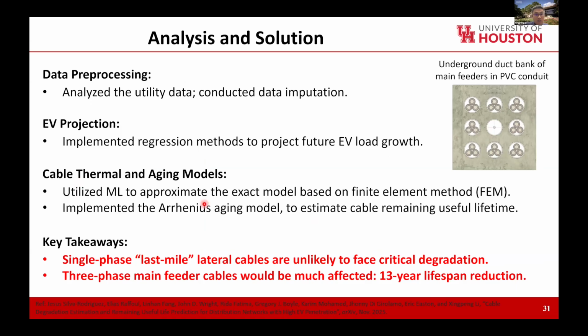I'll jump to the key takeaways due to timing. For single-phase last-mile lateral cables, there shouldn't be any issue. Our analysis shows the increased degradation is less than 1%. But for the three-phase main feeder cables that directly connect to the substation, they could be largely affected, and our analysis shows the cable lifespan would be reduced by 13 years, roughly 20% of its total lifetime.